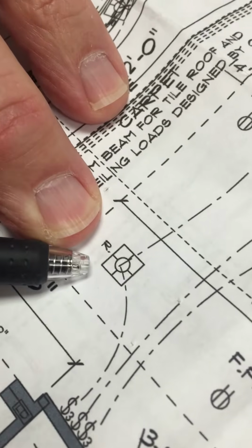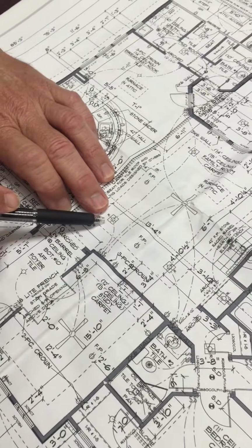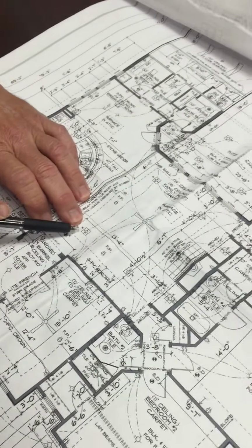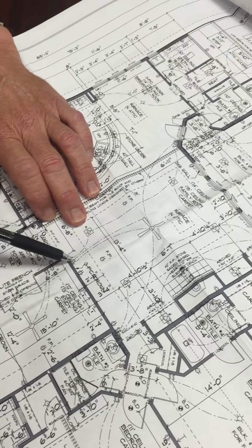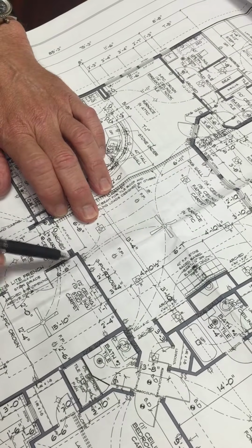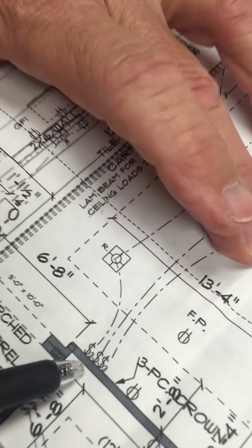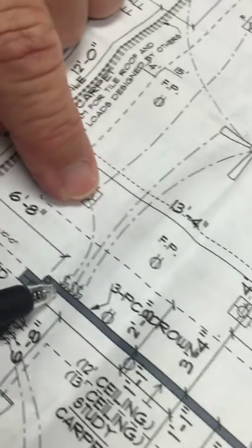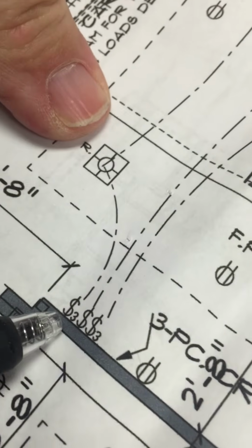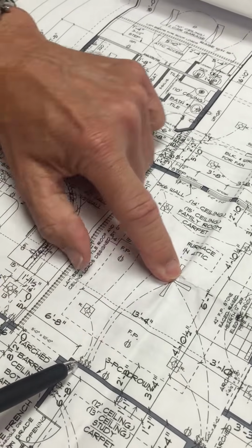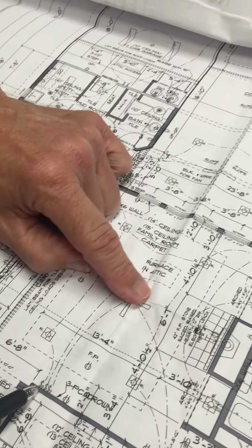You'll see some other symbols in here where it's this box. It's similar to the symbol we saw in the entryway where it's a circle with 4 lines coming off of it. This is boxed, and that is a can light. It is a light that's recessed into the ceiling. It's a recessed can light. You see the R with that. You also see the dash line to the S with a line in it. That is a switch. And if you can really get close in there, you can see a 3, and that's showing that it's a 3-way switch. So where you can switch, it's a big, what they call a 3-gang box that operates not only the can lights, but it operates the ceiling fan and the ceiling fan light.